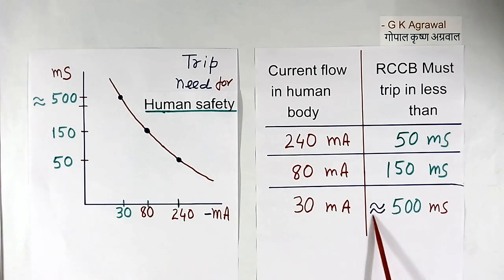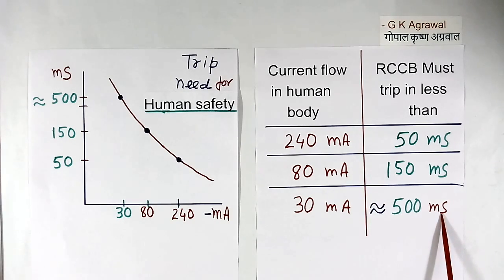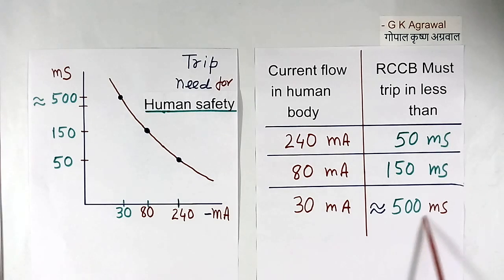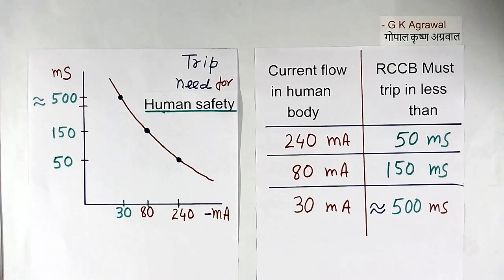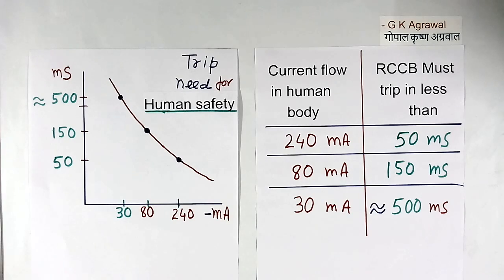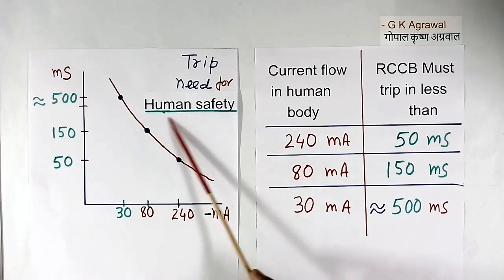This indicates approximately — I was not able to read exactly 500 ms in the plot I saw, so I have shown it approximately. To meet this time requirement, a 30 mA RCCB is used. A 100 mA or 300 mA type RCCB will not trip as per this chart. The 30 mA RCCB is made to meet this requirement for human safety. So we use a 30 mA type RCCB in the house for human safety.